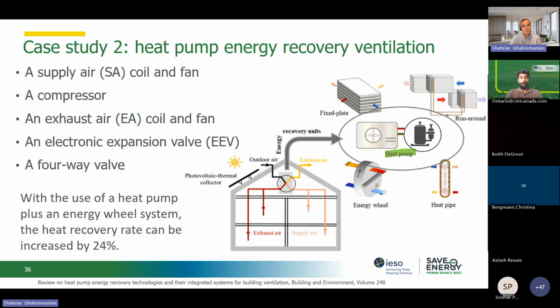So we were discussing the second option, which is similar to the first one, but this is maybe for smaller buildings. So instead of having those recovery systems, let's keep them, but let's add a heat pump. Let's not bring it back. So either it's a wheel or a heat pipe or a heat exchanger or a coil. Let's take that extra heat and recover it through a heat pump. Because the heat pumps transfer the heat and increase the efficiency for us, maybe that's another application that we can think of.